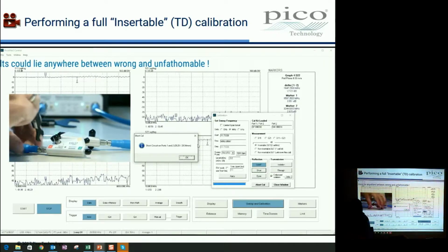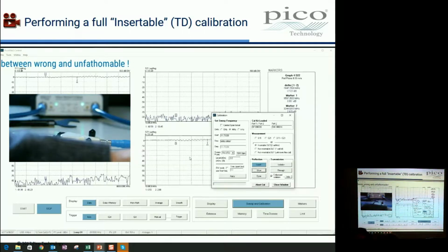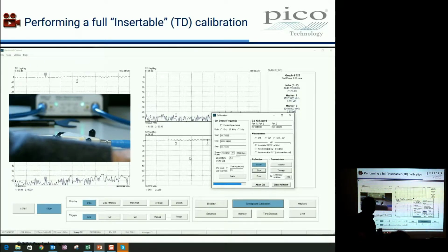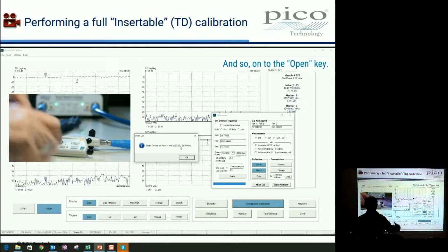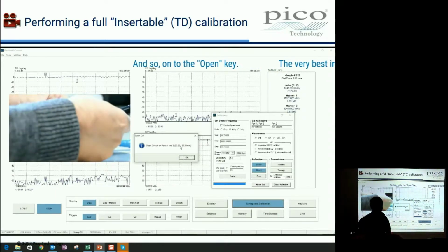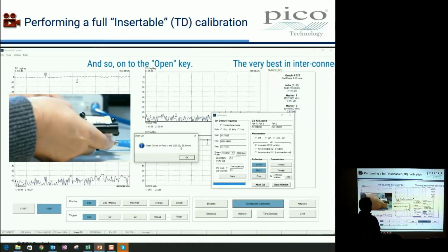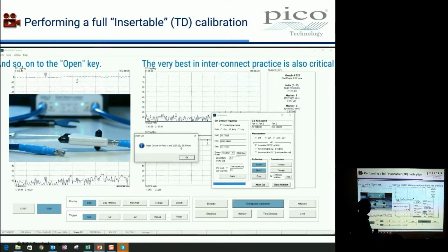And the trouble with getting it wrong is the data that you see on the screen will just send you into a complete spin. You won't know what the data looks like. It's completely unfathomable nonsense on occasion. So you really can be totally misled by making a mistake. So check carefully. Not a process to do in a hurry, which is why I said try to avoid doing calibrations first thing when you need to get the customer settled and tell them all about the product. You don't want to be talking when you're doing this. Not too much anyway.